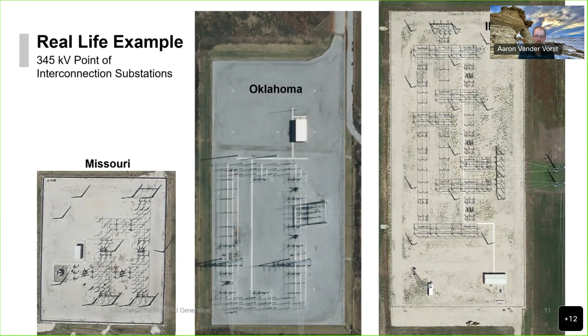On the next slide, I make additional comparisons. For example, all substations start with the same ring bus configuration and are easily expandable to accommodate at least 1 additional connection. However, the last substation pictured requires 2.5 times as much civil construction work and materials, and over 3 times as much bus work. Although this is not the result of a competitive process, these examples illustrate how there can be a stark difference in the design of upgrades.